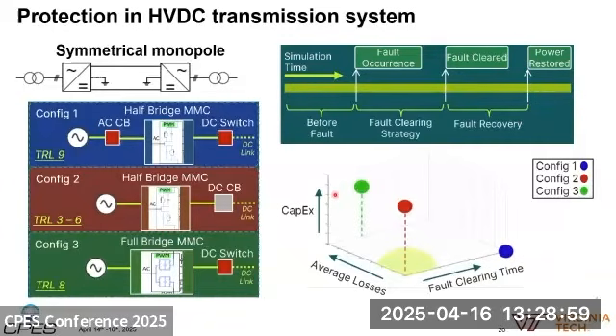This gives us an idea that the percentage of full bridges in the MMC is actually the ability of how well you can block the DC fault. So this remains a design choice: if you want the converter to have higher DC fault blocking capability, you choose a higher percentage; if you don't mind, or you have other system protection methods, you can limit the percentage to something like 5 to 10%.